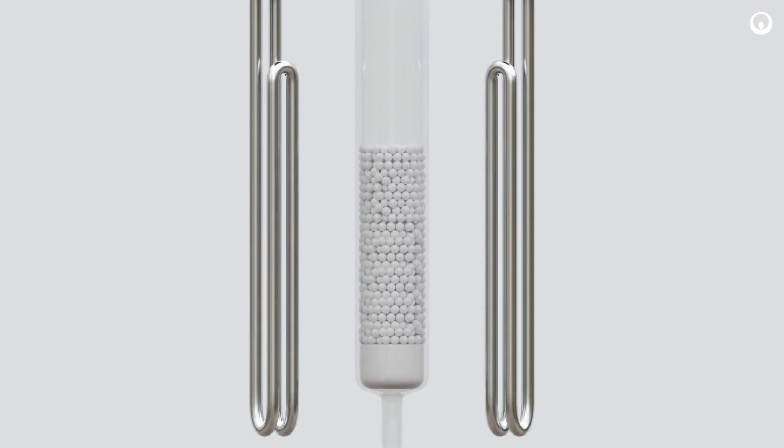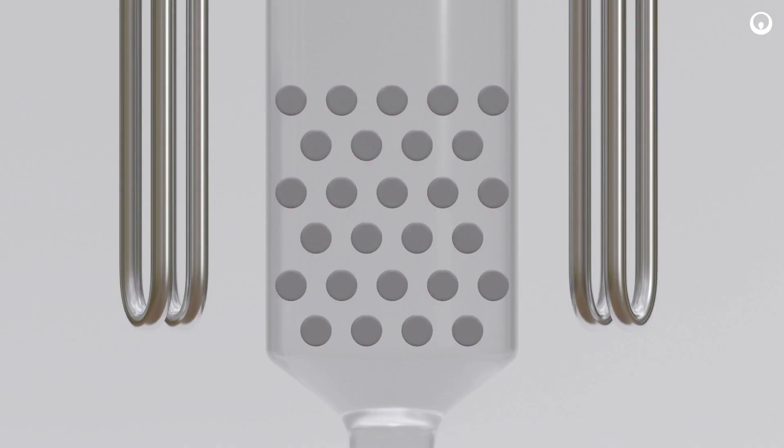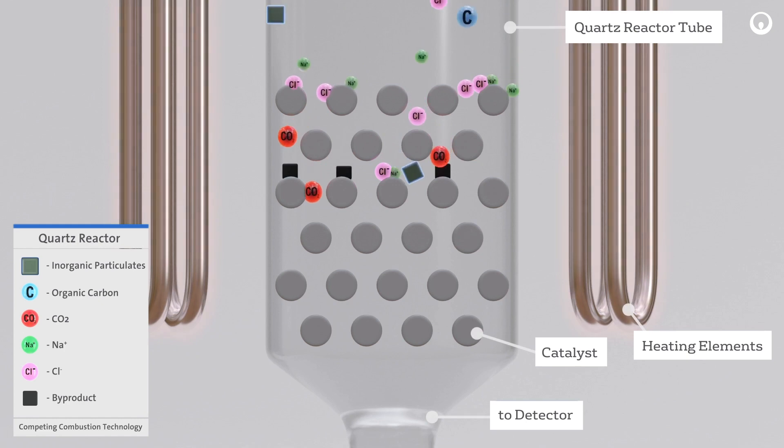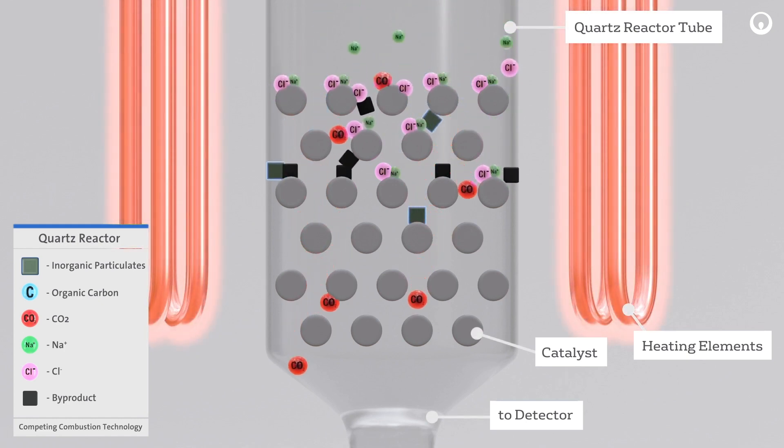TOC analyzers that rely on combustion technology have a quartz reactor that is packed with an expensive catalyst, constantly heated from 680 to 1200 degrees Celsius. Dilution water and sample including inorganic salts and particulates are injected into the reactor. The sample is oxidized with the aid of the catalyst and heat.